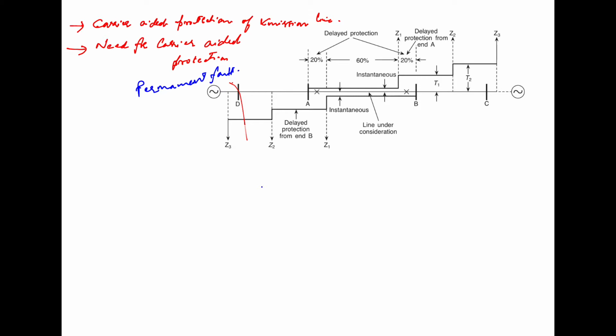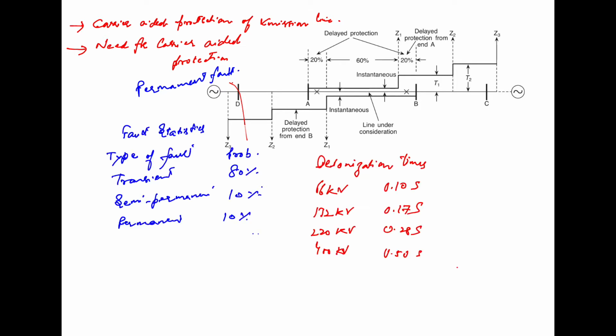However, as we have also discussed, there is statistical evidence that about 80% of the faults are not permanent but are transient faults, and these faults are caused by the breakdown of the air surrounding the insulator, and these faults disappear by themselves if the supply is briefly interrupted and the arc path is allowed to deionize.